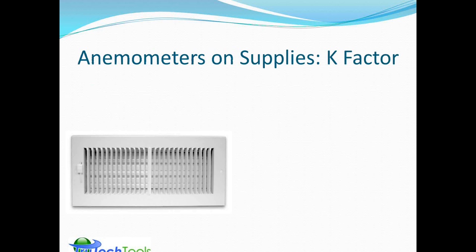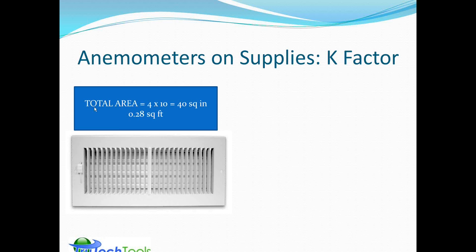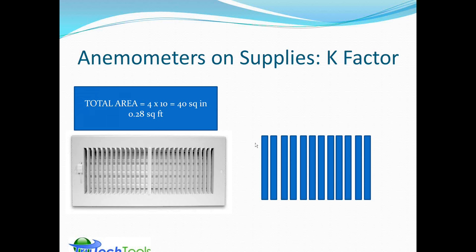When using an anemometer to measure volume flow at a supply, you have to account for the fact that you're not always measuring over a fully open area. You can calculate the total area of the duct, but the grill covering the duct will restrict how much air gets through. The total open area is only a portion of the total area — we call this a K factor or multiplier.